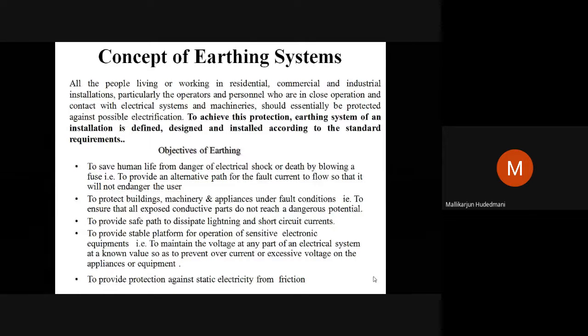This is to safeguard life in residential, commercial or industrial applications. Whenever a person is using electrical equipment or gadgets, and has a chance of establishing contact with the metal enclosures of the gadgets, the safety is earthing. We have to connect the metal enclosures of electrical gadgets to the earth point. There could be an earth pit in the system. In a house, whenever we are trying to get electrification permission, an electrical connection from the corporate office or distribution company, they go for an earth pit. It means we have to dig down the earth pit and process it with a layer of salt. We'll see the diagram. Earth pit maintenance and an earth point need to be established.